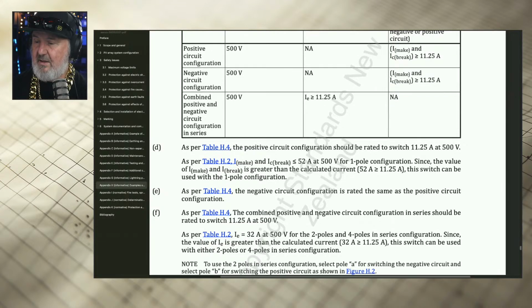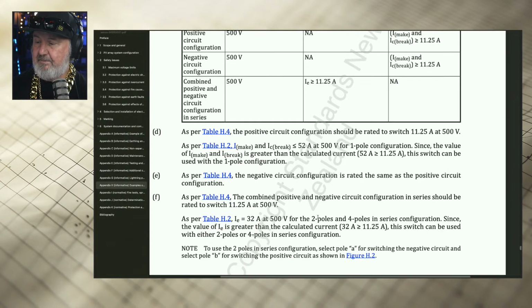So we go down to here and find out, looking up on the table, we've got a 32 amp rating at 500 volts for 2 poles and for 4 poles in series. So 2 poles would be what we're concerned about, and it's way more than the 11.25. So this switch can be used with either 2 poles or 4 poles in series. So either way, it's just fine.